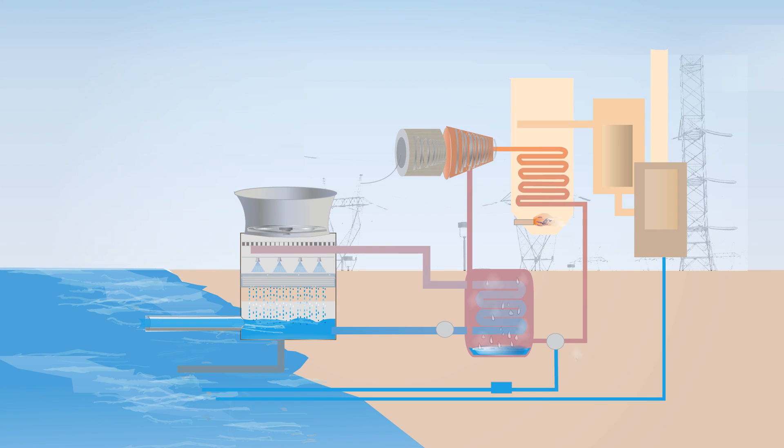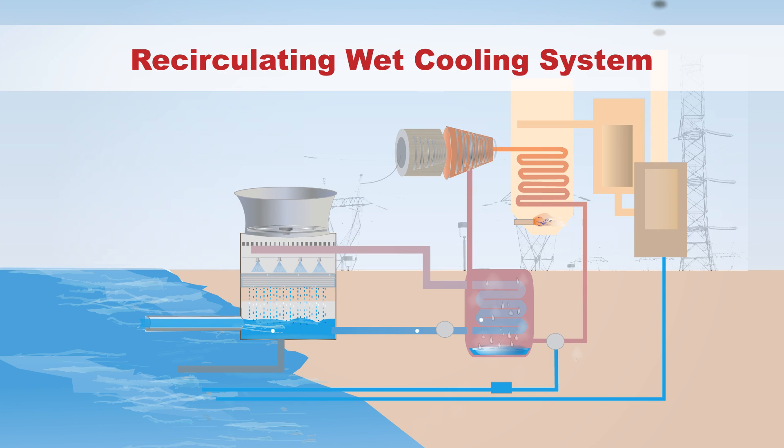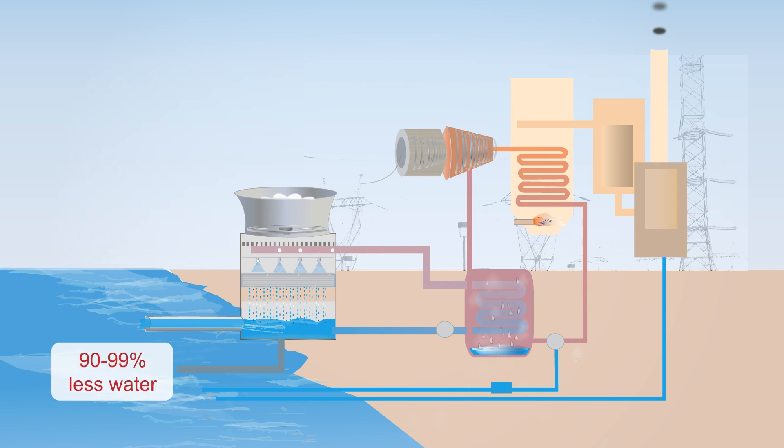The next option is a recirculating wet cooling system. This cooling system withdraws 90 to 99 percent less water than a once-through system, only about 600 gallons per megawatt-hour. However, it loses most of it, 450 gallons per megawatt-hour, to evaporation.